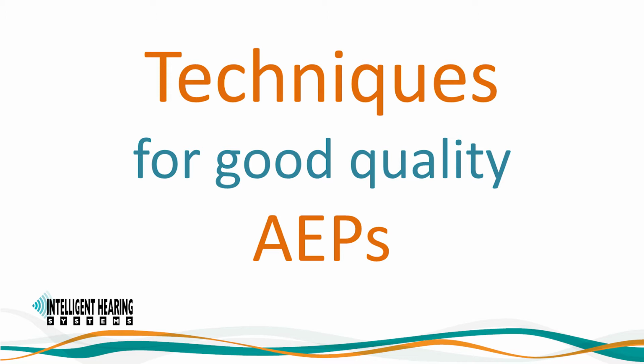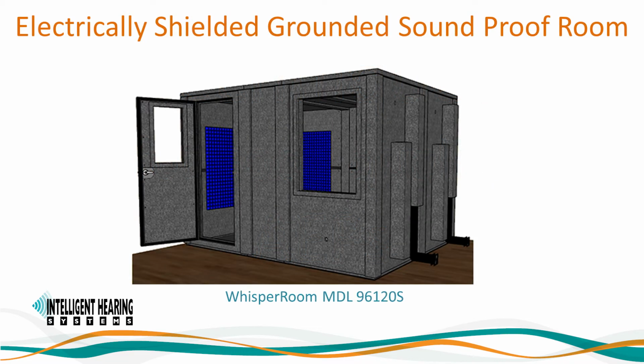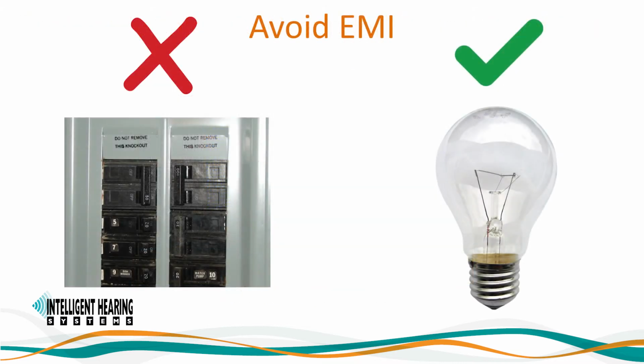Today, I will walk you through techniques for optimizing your Evoked Potential testing setup in order to acquire the best quality EP recordings. Begin by requesting an electrically shielded, properly grounded, soundproof booth or room for testing. If one is not available, then request a quiet room, preferably away from roads, construction activities, MRI machines, and other devices that may produce electromagnetic interference, also referred to as EMI. You should never test in a room containing power lines or breakers. Room lighting should be rated as no EMI.